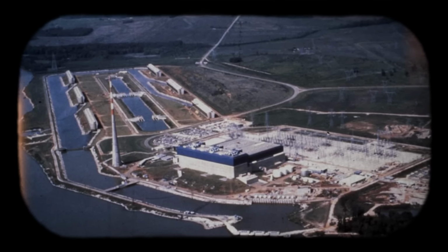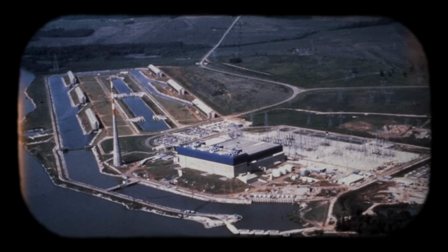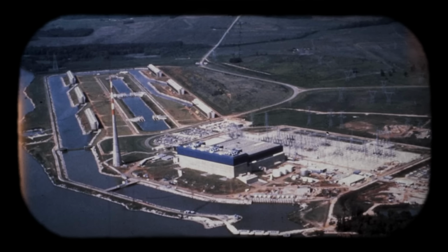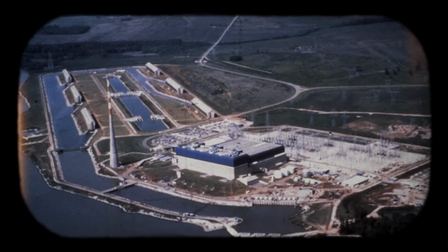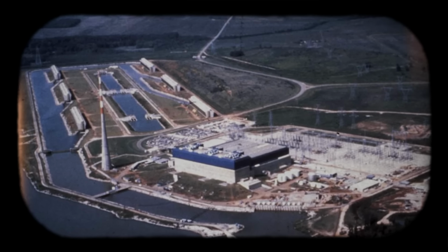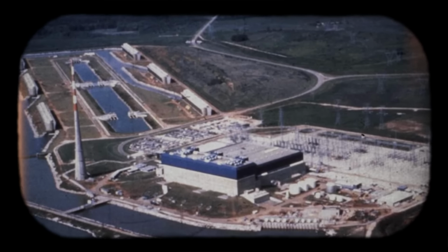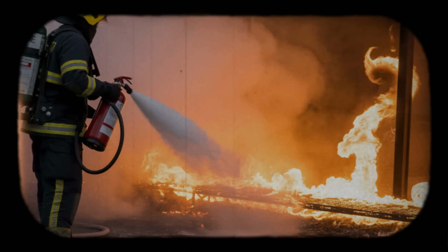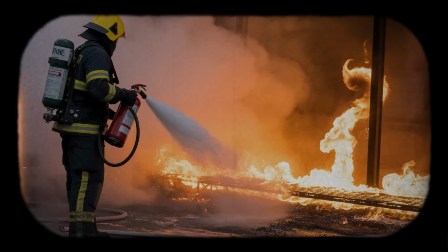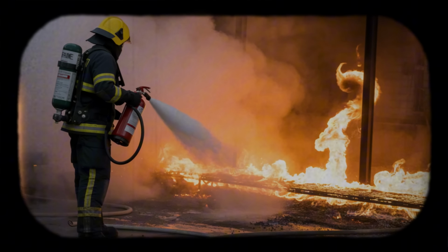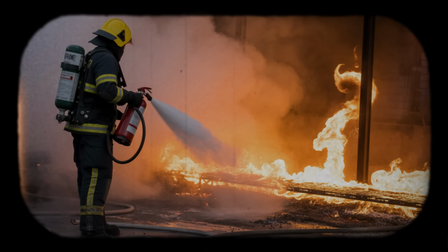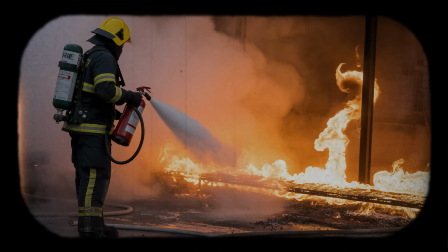TVA implements immediate corrective actions at Browns Ferry. Fire-rated penetration seals replace polyurethane foam at all major cable penetrations. These new seals use intumescent materials that expand when heated, forming a char layer that blocks flame propagation. They are tested and certified to withstand direct flame exposure for specified durations, 1 hour, 2 hours, 3 hours, depending on application. Cable routing undergoes extensive redesign.